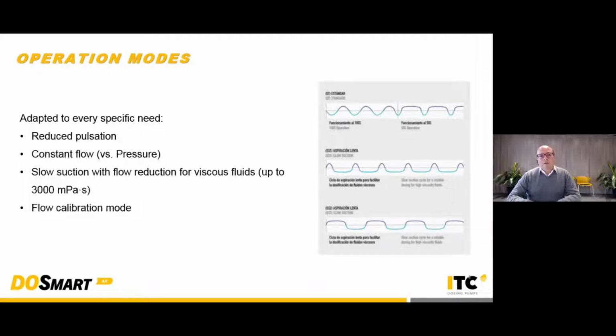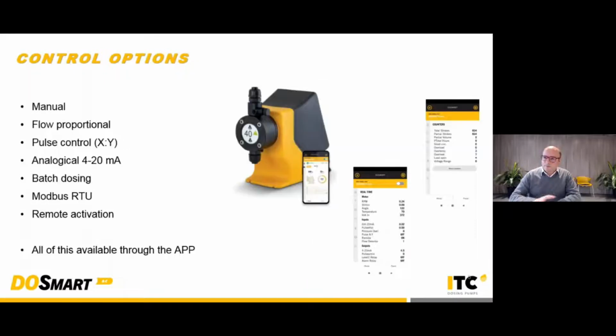And finally, we have a specific mode for pump calibration. What are the control options we have for this pump? We can make it run manually. We change directly the flow of the pump. You will see later in the training lab. But we can modify the flow, as I said, from 1 to 3,000 times.